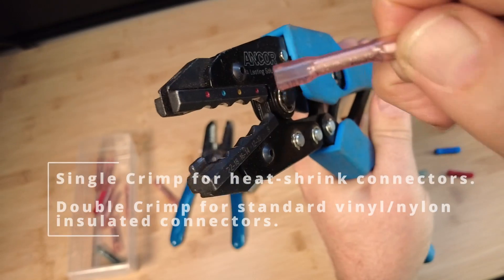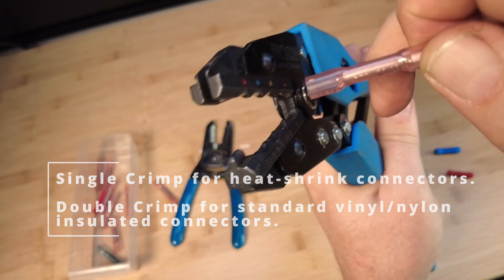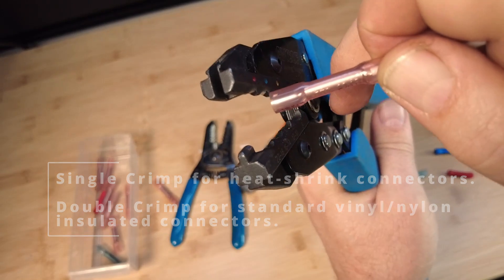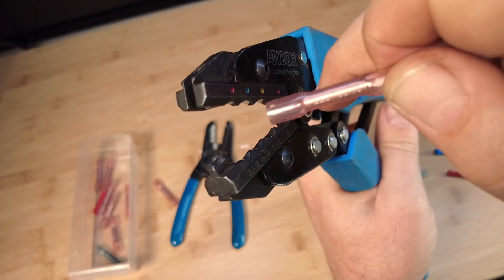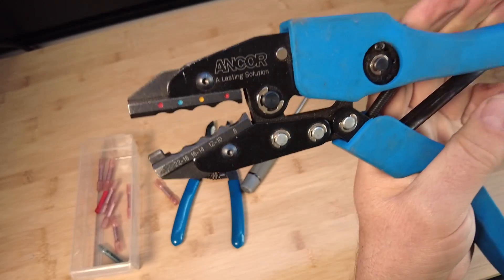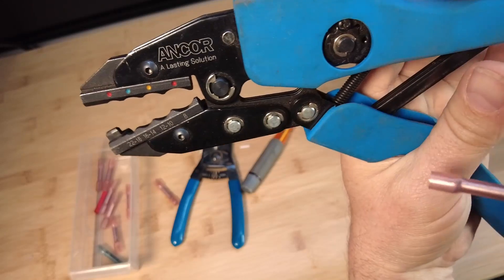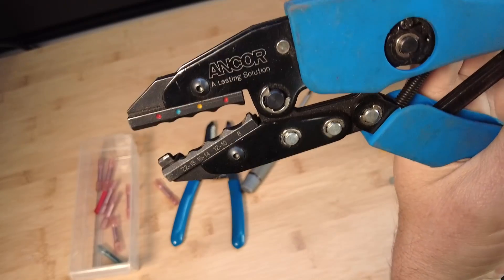You use single crimp if you're using insulated terminals like this. If this doesn't have any plastic on it for insulation, then you'd use a double, but we don't want to puncture the insulation. So we're using a single crimp version. These are ratcheting, so they have a bit of extra leverage to them. So it makes it easier to crimp it.